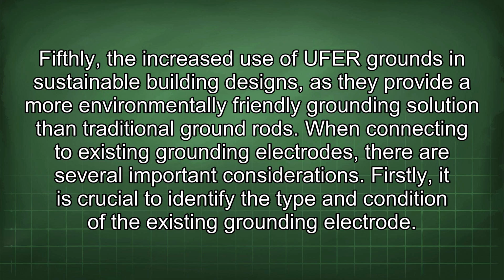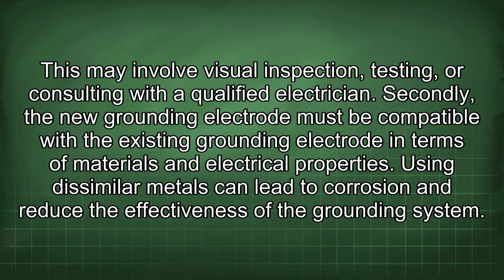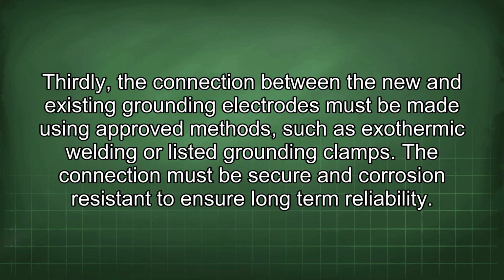Firstly, it is crucial to identify the type and condition of the existing grounding electrode. This may involve visual inspection, testing, or consulting with a qualified electrician. Secondly, the new grounding electrode must be compatible with the existing grounding electrode in terms of materials and electrical properties. Using dissimilar metals can lead to corrosion and reduce the effectiveness of the grounding system. Thirdly, the connection between the new and existing grounding electrodes must be made using approved methods such as exothermic welding or listed grounding clamps. The connection must be secure and corrosion resistant to ensure long-term reliability.